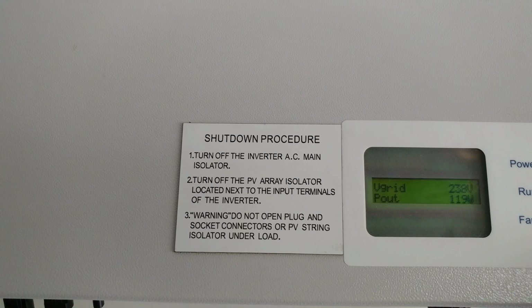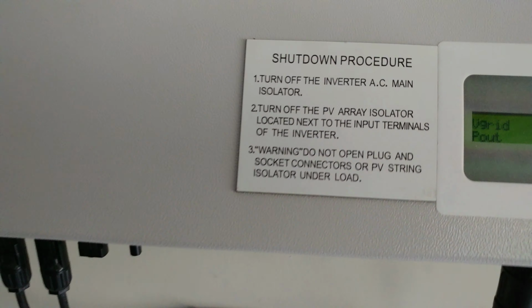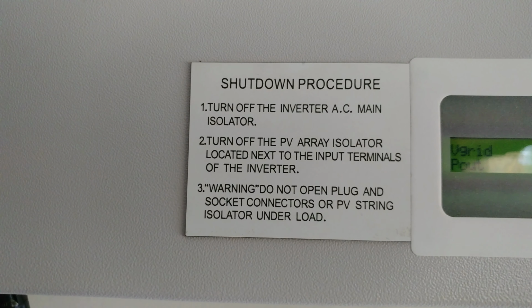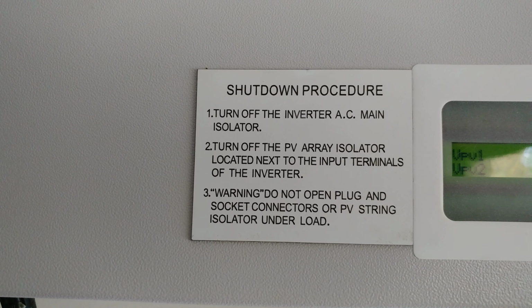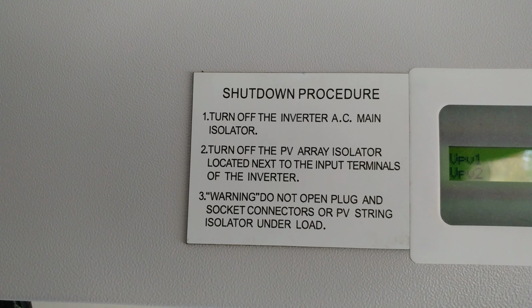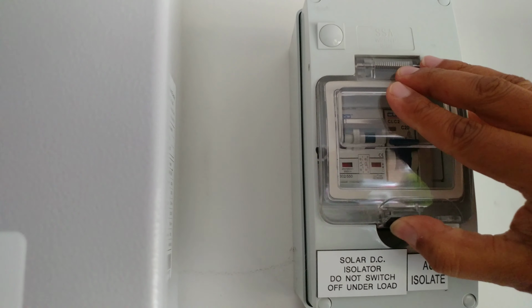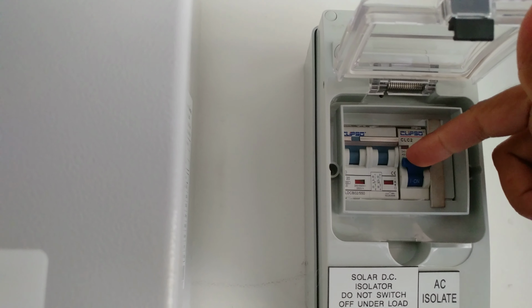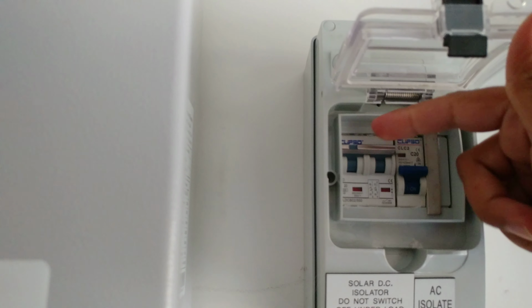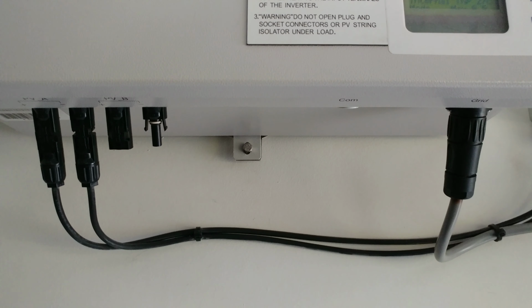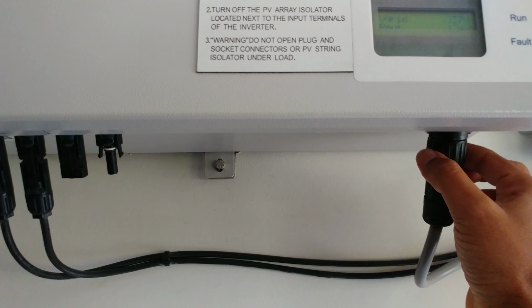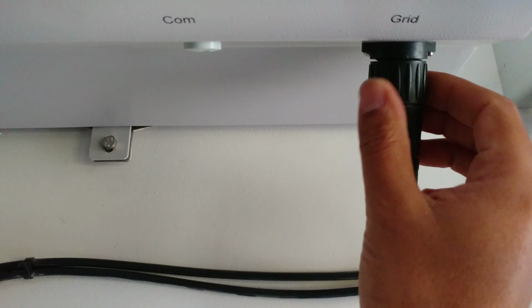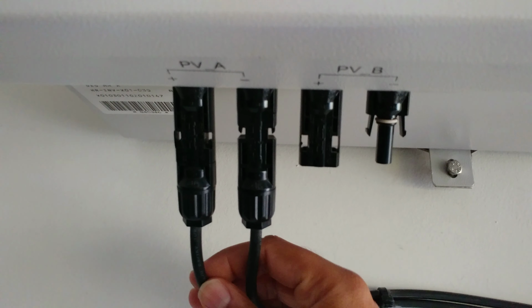So what I had to do was turn off this inverter following this procedure. And if you have a look, turn off the inverter AC main isolator and then the solar array. So here's the switch. And all I did was I just turned it like that. Turned off, this is the AC one and then the DC one. Once that was done, I was able to disconnect this inverter by unscrewing this terminal here, and the solar DC inputs.